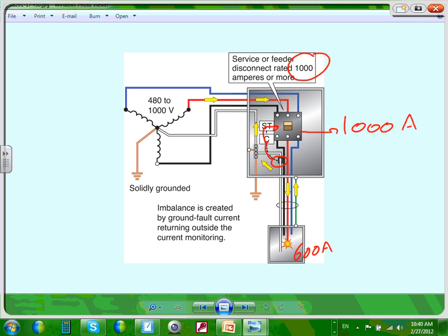Remember, guys, if you have a three-phase system, the current is supposed to be balanced. What comes in must come out on the neutral. If the current is mismatched and the neutral is not carrying what's coming in, it will realize something is going somewhere else. Where is it going? Through the ground. There's a differential that takes the value and analyzes it in the electronic circuit and trips the circuit breaker. Who cares? It will protect your system from a low current ground fault. It's required on every system that's 1,000 amp or higher, 480/277.